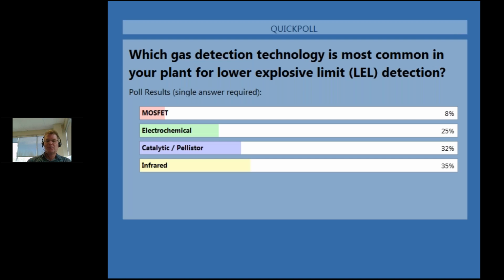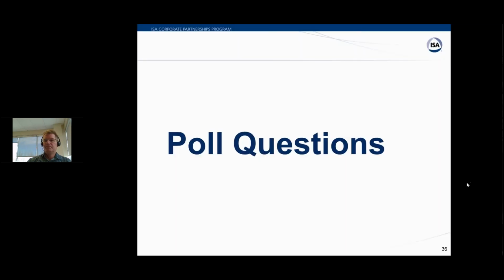So that's pretty much what I expected. I'm great to see that the infrared is picking right up, probably for the reasons that it is a little less sensitive to other conditions, lower maintenance because there are no moving parts, so to speak, and calibration might be a little bit less. There are probably more electrochemicals than you think, because all your little personal gas monitors, pretty much all of those are going to be electrochemical. But yes, your installed point detectors, that's great stuff. Thank you.